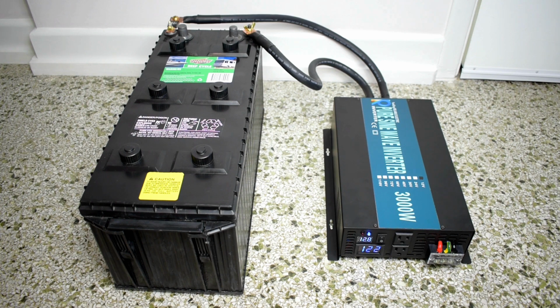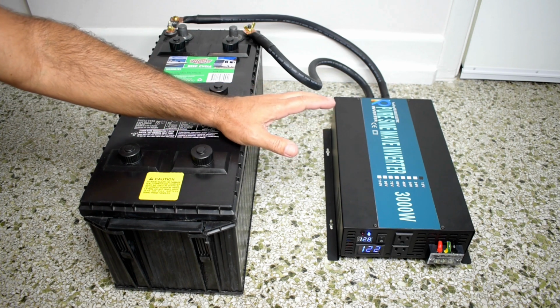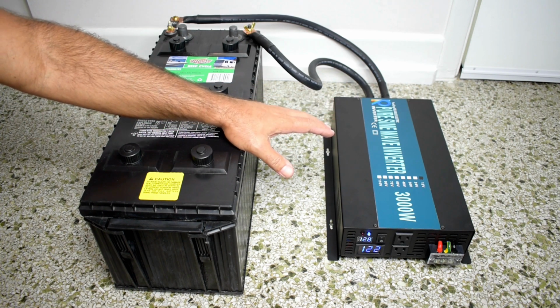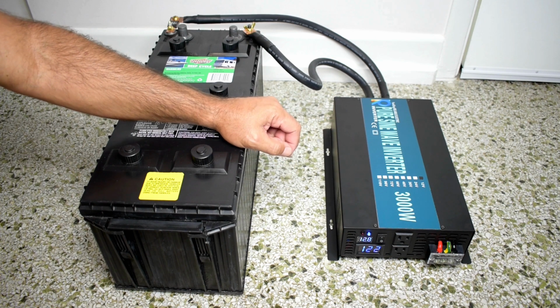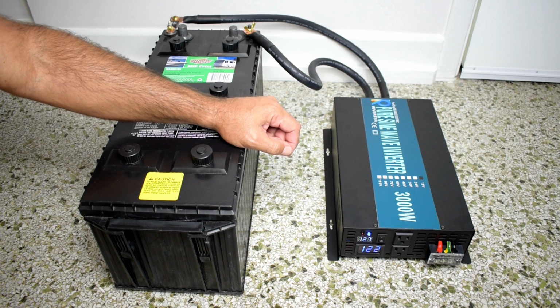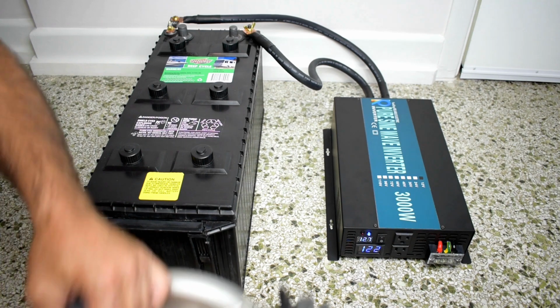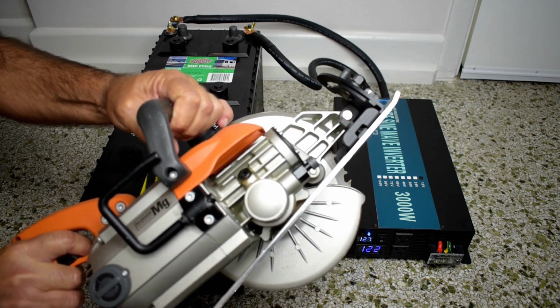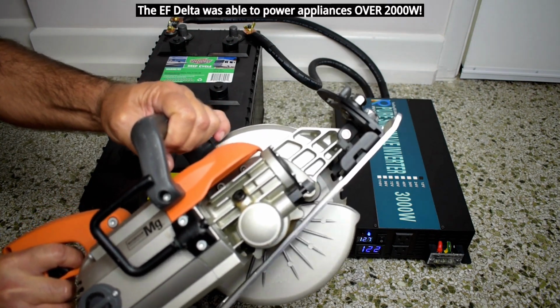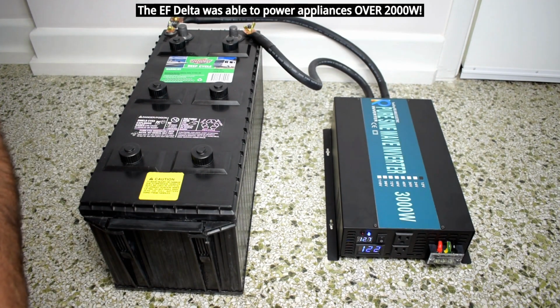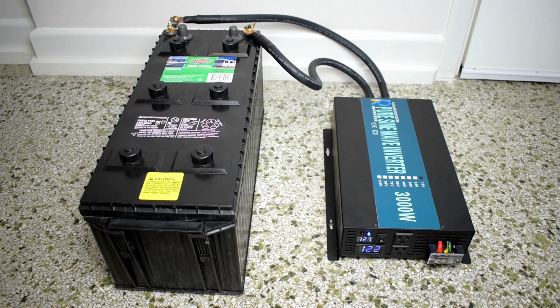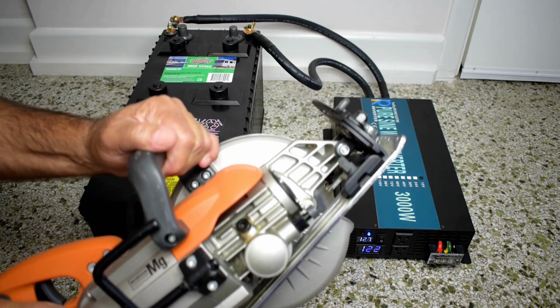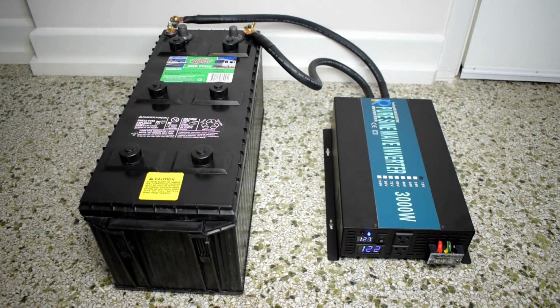Now for the next test, I want to see how well this powers inductive loads such as a motor or a transformer. In a previous video when I tested the EcoFlow Delta, this saw you see right here, it would not power this saw. The saw is 15 amps and it has extremely high inrush current, but it was able to power a microwave oven. So if this inverter can handle this, you know it's going to handle a large microwave oven as well as your refrigerator. Let's give it a try.